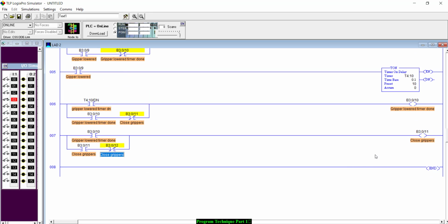Now, grippers open, grippers closed. Even if somebody opens the door when this is triggered, most likely those grippers are going to continue to close because they happen so fast. These are driven by pneumatics or hydraulics, usually pneumatics, and they happen so fast that even if you open up the door in the middle of that process, most likely it still closes the grippers. And that information would stay active until you told the grippers to open anyway. So you'd be okay with all that information.